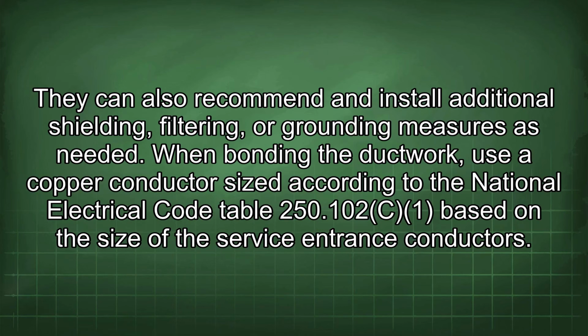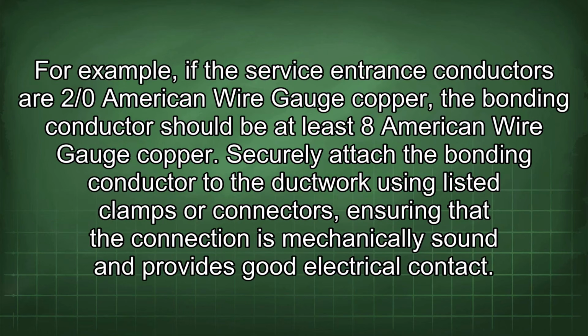When bonding the ductwork, use a copper conductor size according to the National Electrical Code Table 250.102 based on the size of the service entrance conductors. For example, if the service entrance conductors are 2/0 American wire gauge copper, the bonding conductor should be at least 8 American wire gauge copper. Securely attach the bonding conductor to the ductwork using listed clamps or connectors, ensuring that the connection is mechanically sound and provides good electrical contact.